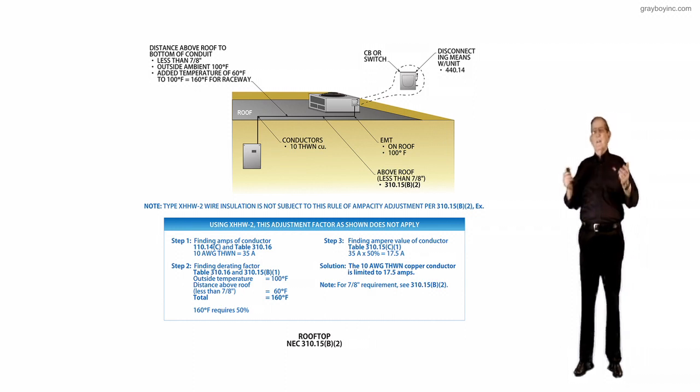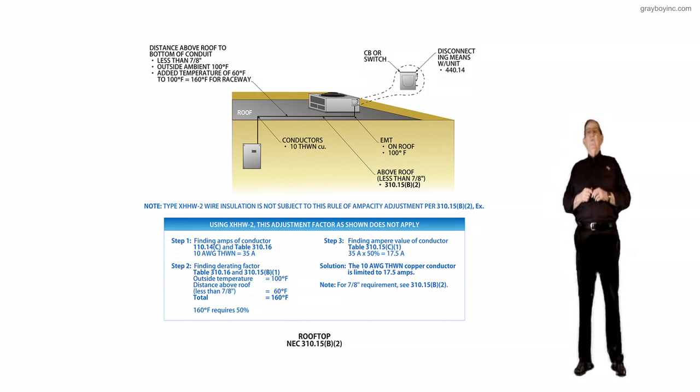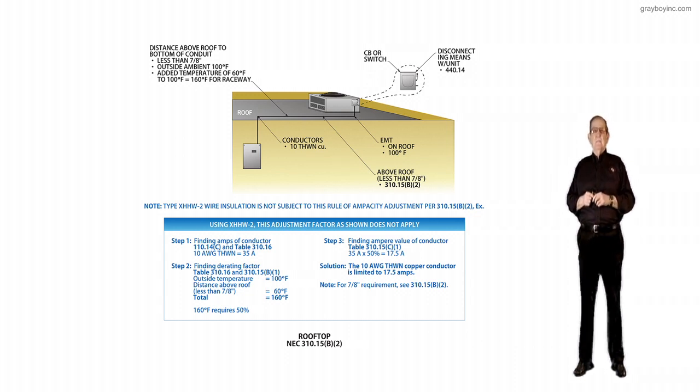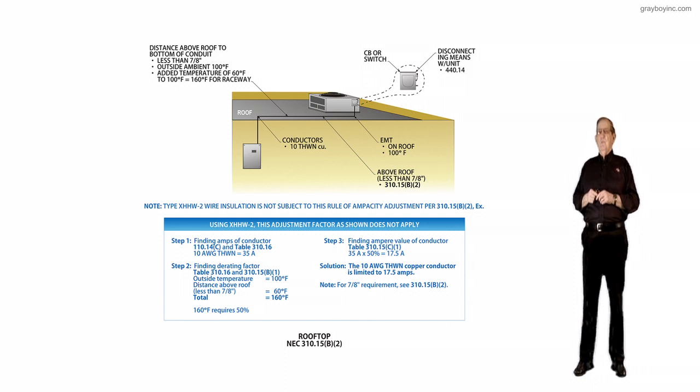You'd say, man, I can't afford that. I'm here in Arizona, the temperature is just very hot during the summer, so I'm just going to use XHHW slash 2. And if we see the 310.15B2 exception, it says if you use that, then it doesn't matter. A lot of your engineers will use XHHW slash 2 and they don't get into the derating factors, and most authority having jurisdiction recognizes that. So you see in the note, type XHHW slash 2 wire insulation is not subject to this rule of ampacity adjustment for 310.15B2 exception.